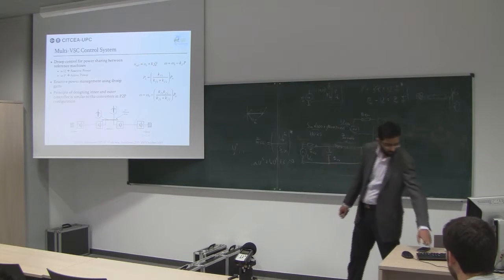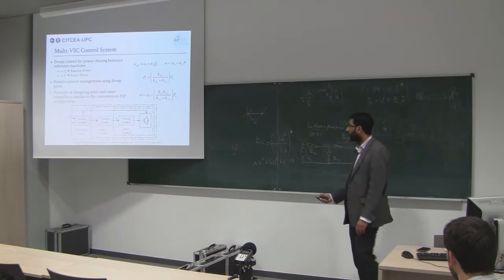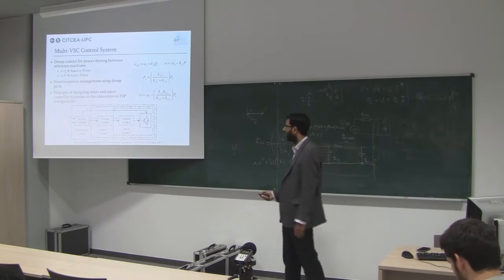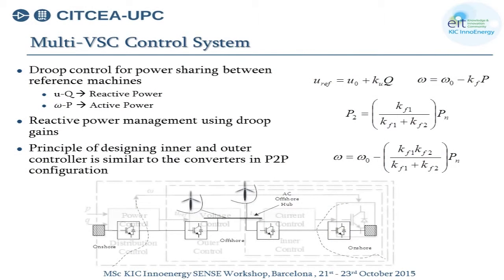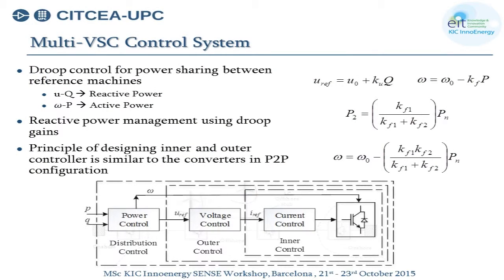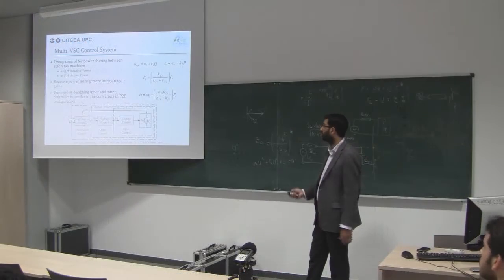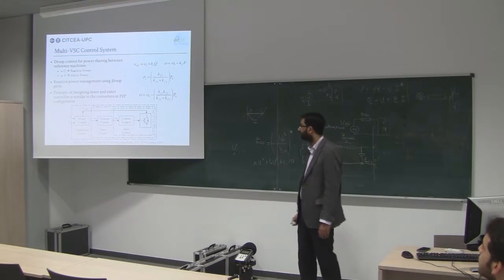So the control mechanism could look like this. You have internal current control, and then voltage control, like a point-to-point configuration. When you want to connect to the multi-infeed configuration, you have a distributed control system depending on this droop concept, and then you can control the power sharing between two converters by setting these gain values.